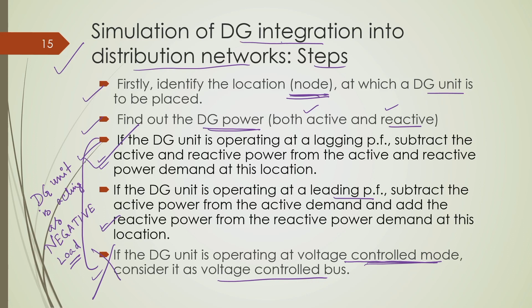In one case, if the DG is supplying reactive power as well, you can subtract this reactive power from the reactive power demand, but if it is operating at leading power factor condition or needs reactive power to operate, you add this as additional reactive power demand. And if it is operating in voltage control mode, which is very rare, you can consider the voltage magnitude of the bus as well. I did not consider that exercise; I considered a typical DG unit that provides both active and reactive power.